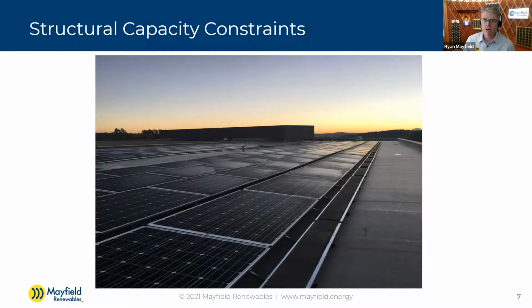So that's a good segue into another constraint we're going to talk about today: structural capacity restraints. People are probably pretty well aware of this for rooftop systems specifically. You're putting ballast down, an array down, racking down, ballast pans down, and ballast in the pans—so you're adding, in some cases, a significant amount of weight, and not all buildings can support that. Getting back to some earlier points, you can see in this picture a very low tilt array—the tilt angle keeps the wind loading down and really helps distribute that weight. So that's always another constraint, and it can directly affect the size of your system.